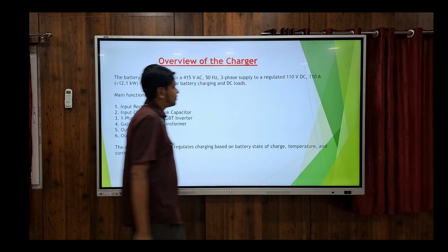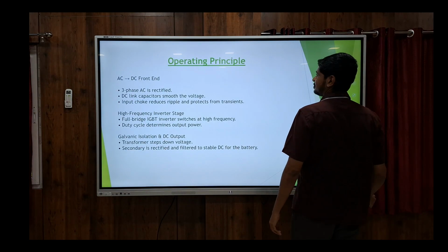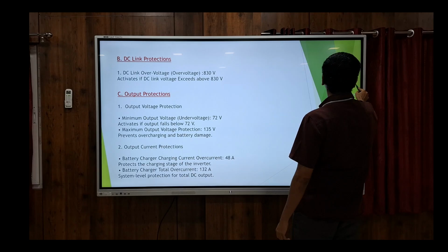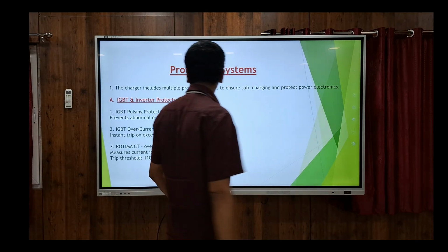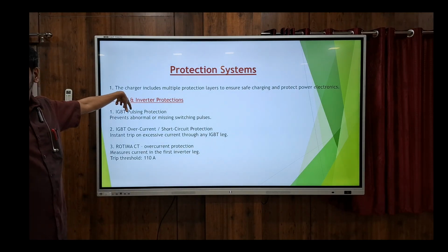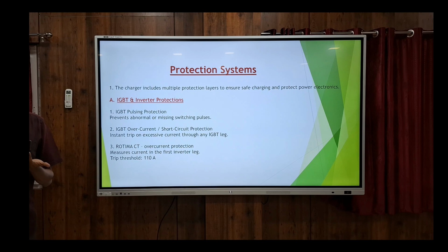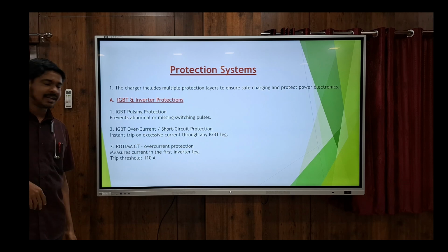Now we will come to the circuit. Before that, I can also tell some protections. Since IGBT is in this circuit, there is pulsing protection: if the IGBT is misbehaving and, instead of pulsing intermittently, it is pulsing continuously, a gate drive unit card is there. It monitors all these parameters and protects. Voltage is monitored, DC link voltage is monitored, output current is monitored, everything is monitored, so everything is equipped with protection. Temperature protection is also there. Then a CT is there for current protection, which I will explain later.